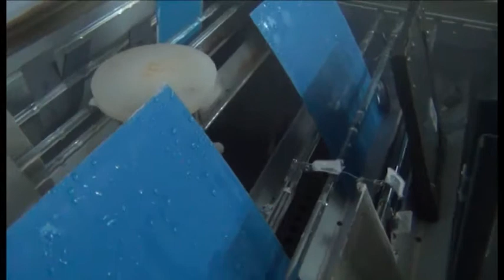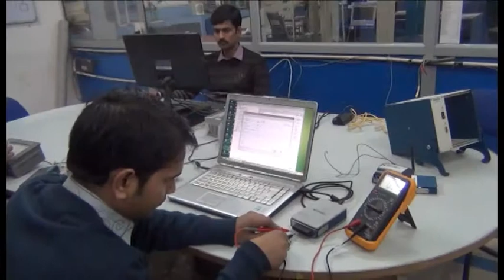This method is intended to provide a more realistic simulation of the interaction of factors than is found in traditional tests with continuous exposure to a static set of corrosive conditions. The maximum transition times between each part of the test cycle can be programmed through our user-friendly program to meet the industrial standards. Our teams of engineers are working on different software and hardware to create multiple options and to look for the most efficient and cost-effective alternative.